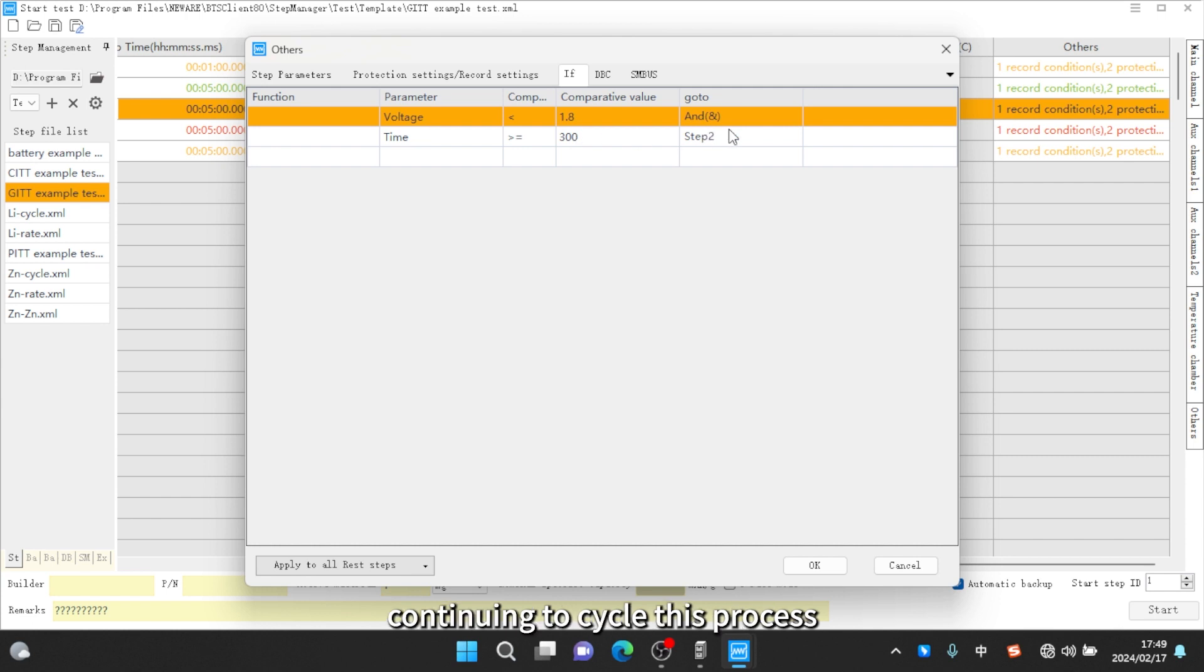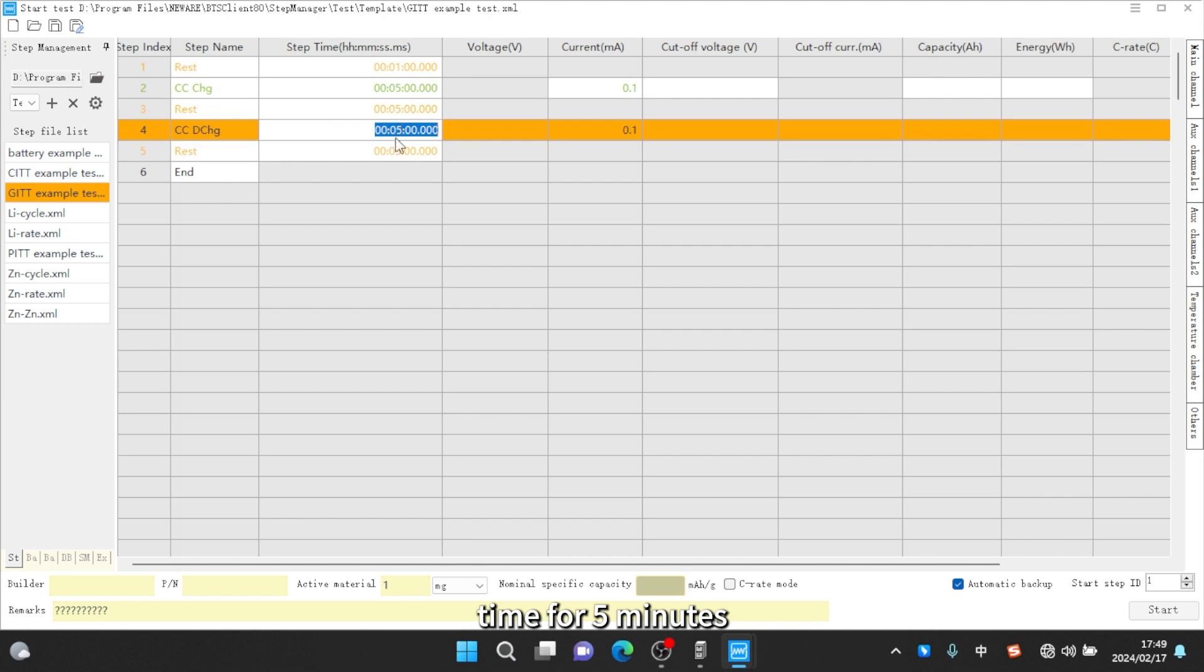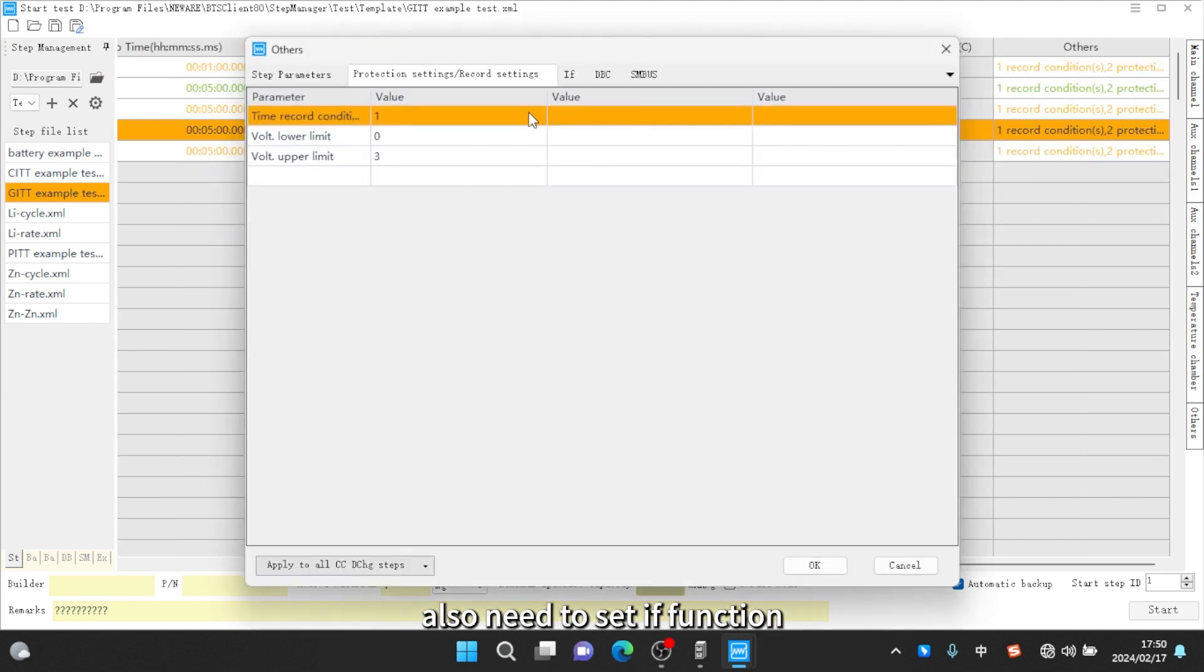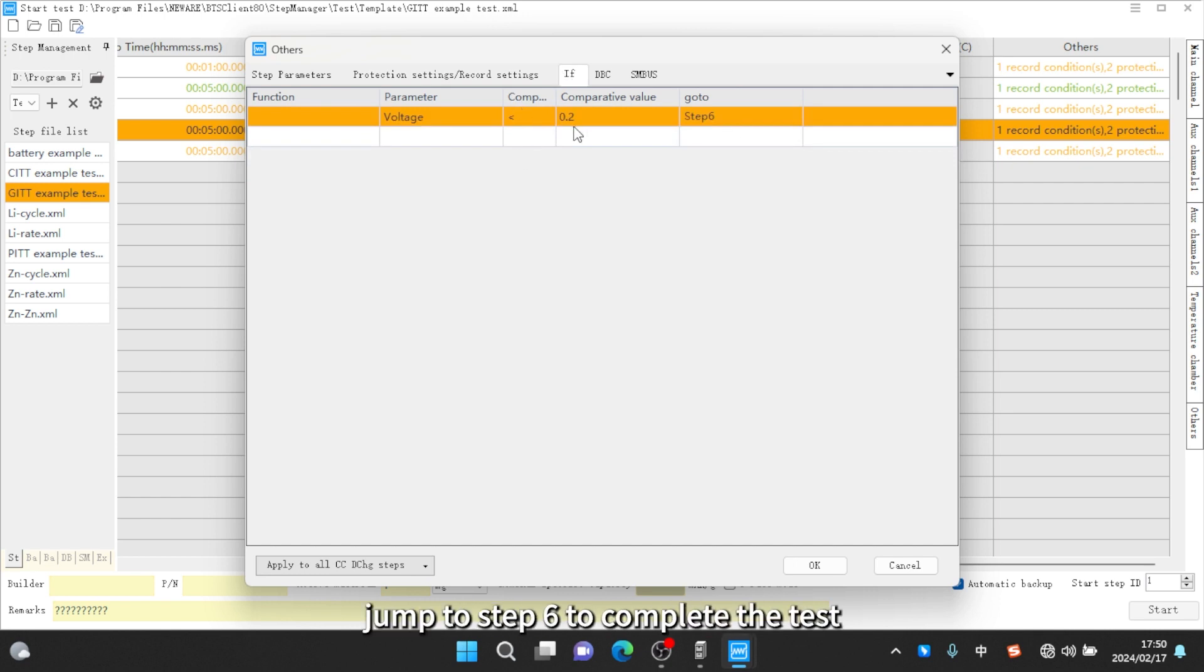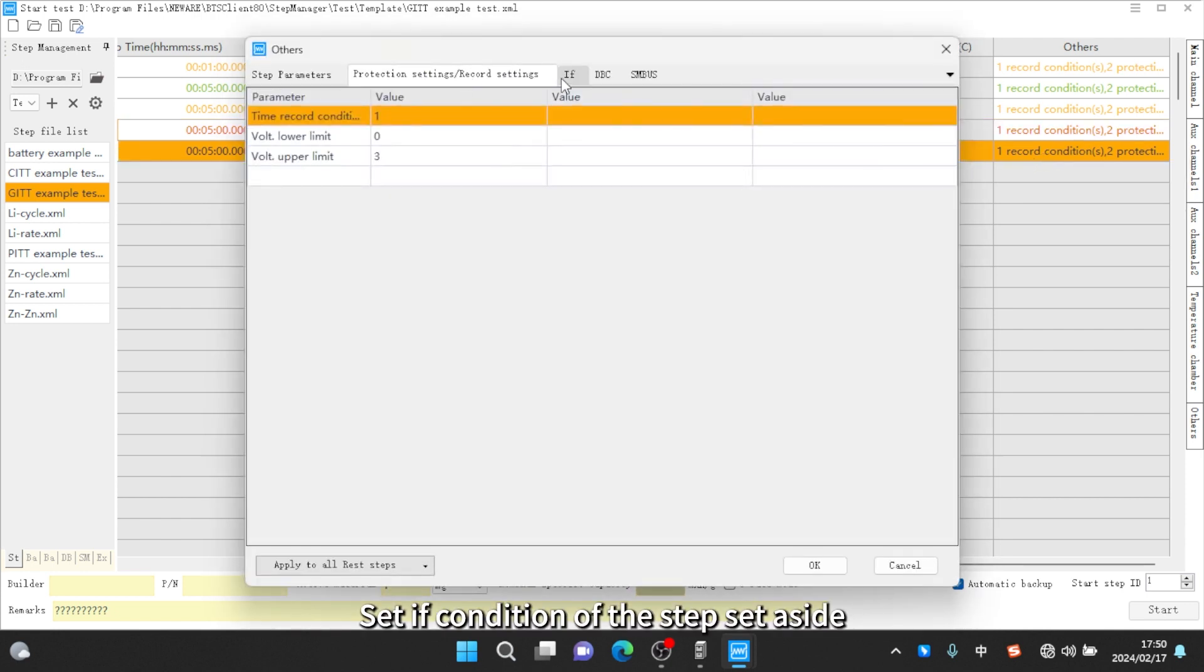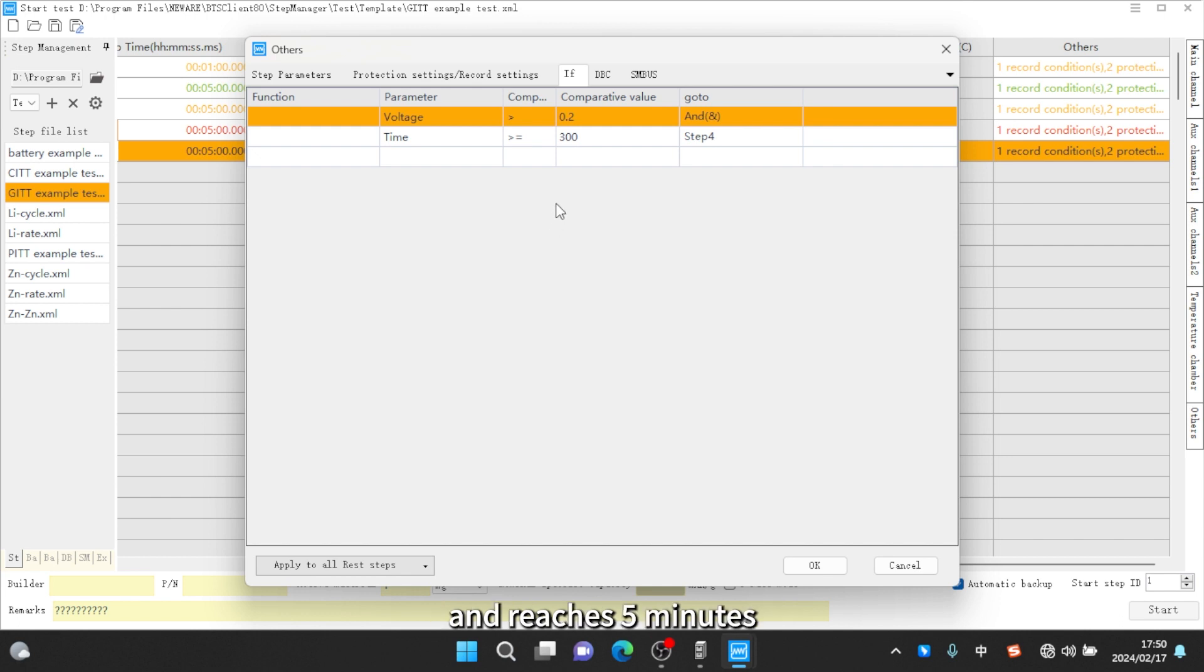Set constant current discharge time for five minutes and rest time for five minutes. Also need to set an IF function: when discharge voltage is less than 0.2V, jump to step 6 to complete the test. Set IF condition of the step set aside: when it is greater than 0.2V and reaches five minutes, jump to step 4 to continue to cycle this process.